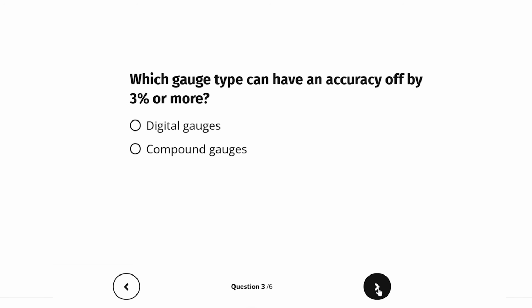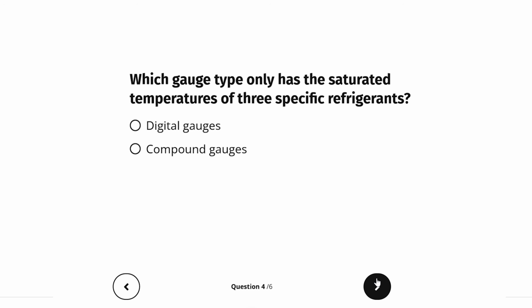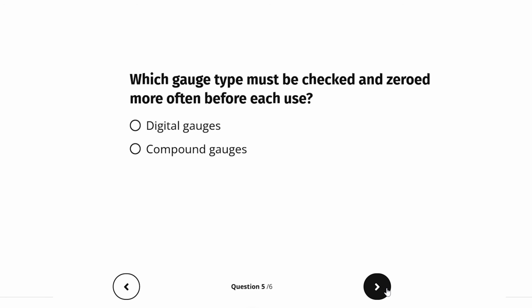Which gauge type can have an accuracy that's off by 3% or more? The answer for that is compound gauges. Which gauge type only has the saturated temperatures of 3 specific refrigerants? The answer for that is compound gauges. Which gauge type must be checked and zeroed more often before each use?